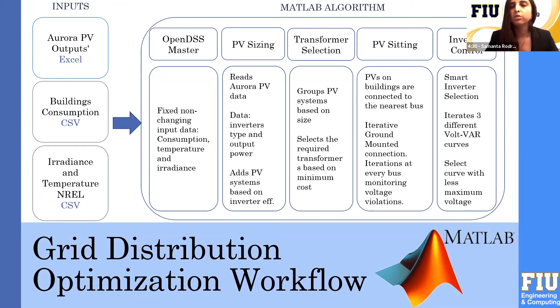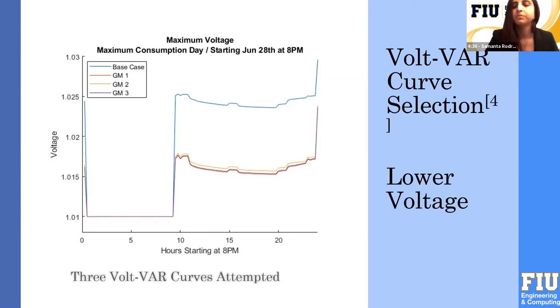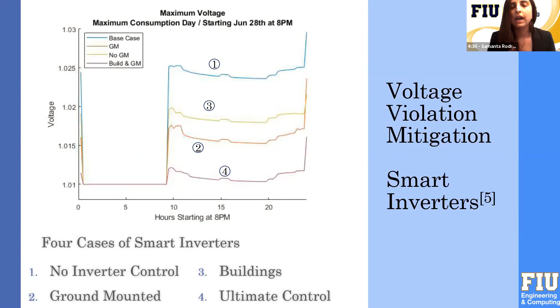We decided to use inverter control to reduce the maximum voltage of the system and also to avoid damaging the equipment due to unexpected voltage peaks. For the inverter control, we tested 3 different volt-var curves. All of them were tested in the ground-mounted system, and the first one is the one that showed the greatest reduction in maximum voltage. This curve was tested in 3 different cases, and the last one is the most beneficial for us with the reduction in voltage and is installed in the ground mount and in most of the buildings.